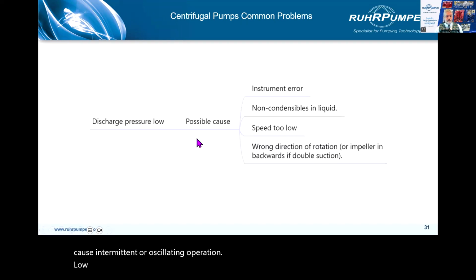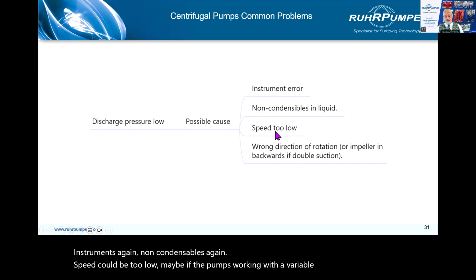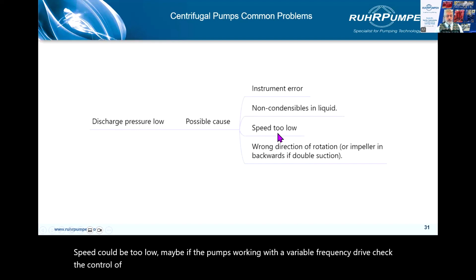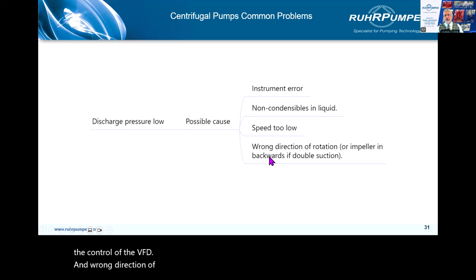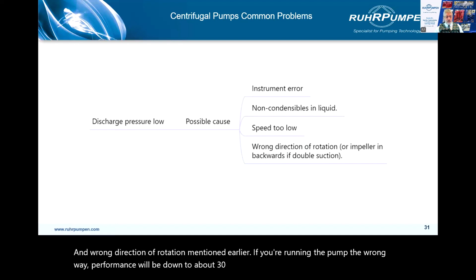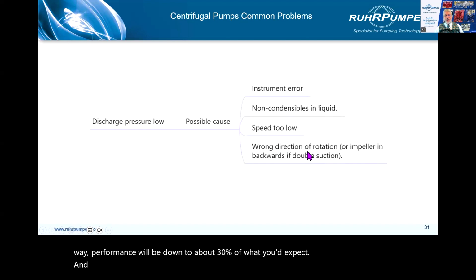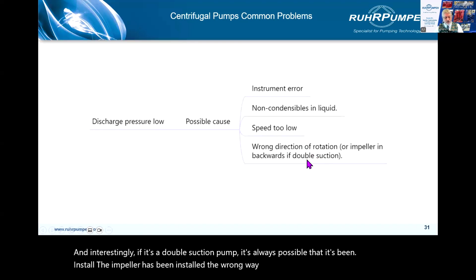Low discharge pressure. Instruments again. Non-condensables again. Speed could be too low. Maybe if the pump's working with a variable frequency drive, check the control of the VFD. And wrong direction of rotation. I mentioned earlier, if you're running the pump the wrong way, performance will be down to about 30% of what you'd expect. And interestingly, if it's a double suction pump, it's always possible that the impeller has been installed the wrong way round. That's another one to remember.